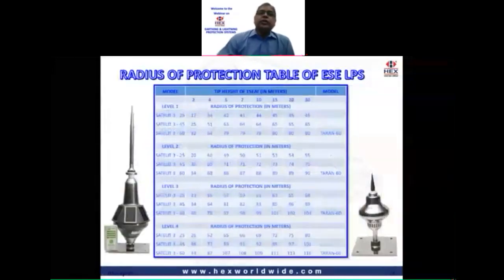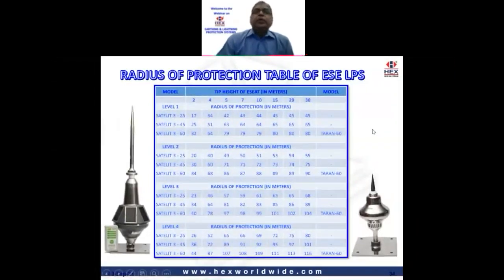This is the table given by the NFC standard for the radius of protection provided by each ESE LA. If the tip of the ESE is installed at a height of 5 meters from the highest point of the structure, for level one, both the Satelit 3 and the Taran 60 models will provide a radius of protection of 79 meters. Everything within that circle is protected. Similarly, for level 2 it will be 86 meters, for level 3, 97 meters, and for level 4, 107 meters. So each instrument can provide you, as per the lightning protection level, these radii of protection. Just one instrument.